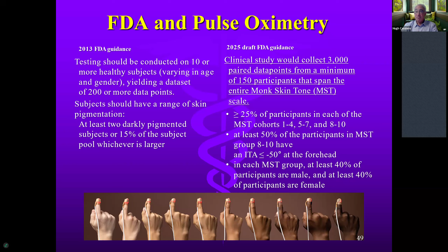Not only that, but we're going to require you to have from 1 to 4 lightly pigmented cohorts, 25% of the people you check, the 5 to 7 moderately pigmented, at least 25% represented in that group, and then the 8 to 10, the highly pigmented people, you need to have at least 25% of your cohort tested in that group. So not only subjective and objective measures, you need to have the right amount of people in those buckets to make that calibration curve. Again, just to emphasize the difference between before and after, the 2013 guidance document was really loose, which is why we still have an issue with pulse oxes on the market.